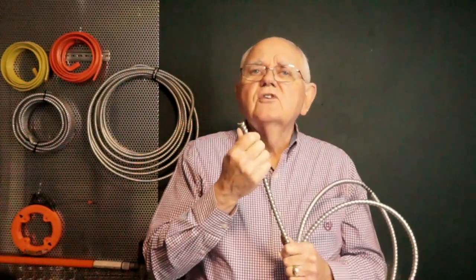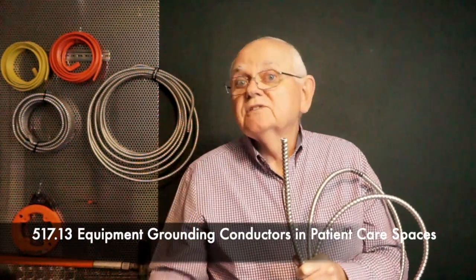And we say, oh, that's for healthcare facilities. Well, okay, let's talk about that a little bit. Now, there's nothing in the code book that says I have to use green, or in the UL standard, or in fact in NFPA 99 for healthcare facilities, that says I have to use metal-clad cable with a green outer finish in healthcare facilities. In healthcare facilities, Article 517 is going to take us to 517.13.